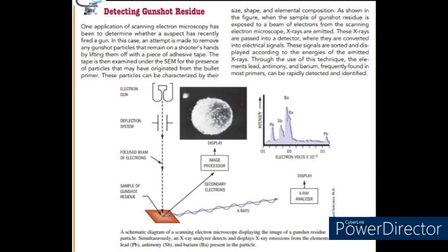of collision. Another facet of scanning electron microscopy has been the use of X-ray production to determine the elemental composition of a specimen. X-rays are generated when the electron beam of the SEM strikes a target. When the SEM is coupled to an X-ray analyzer, the emitted X-rays can be sorted according to their energy values and used to build up a picture of the elemental distribution in the specimen. Because each element emits X-rays of characteristic energy values, the X-ray analyzer can identify the elements present in the specimen. Furthermore, the element's concentration can be determined by measuring the intensity of the X-ray emission.